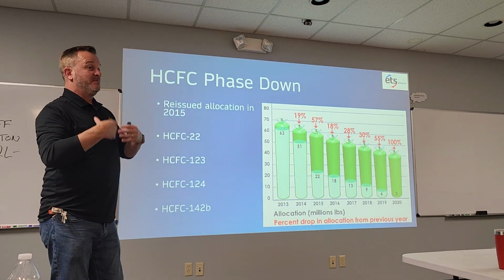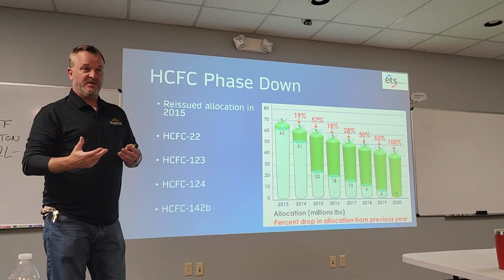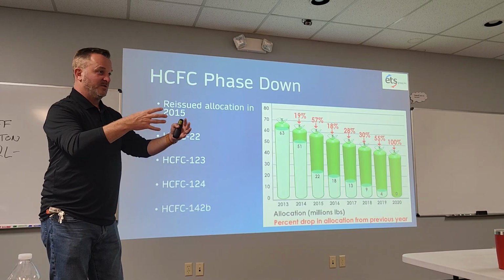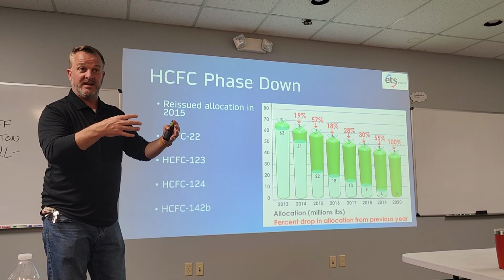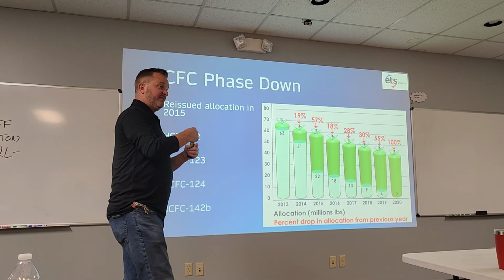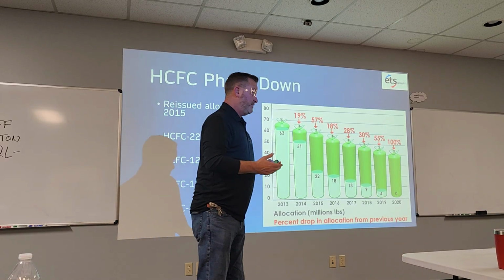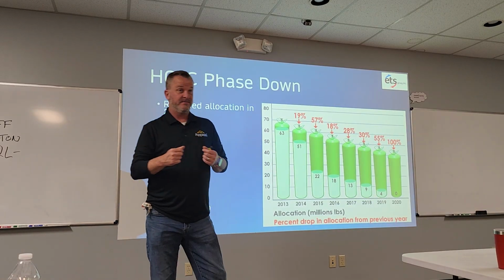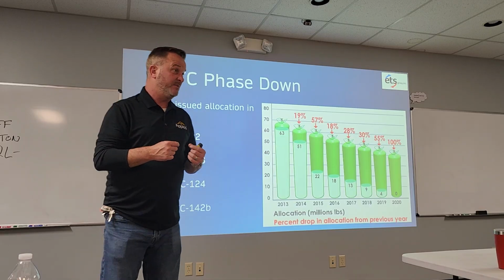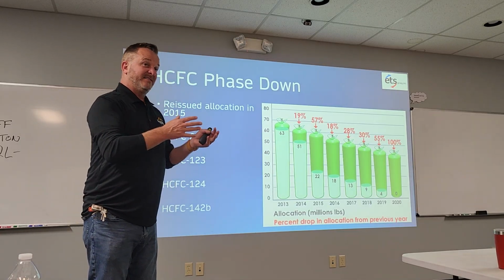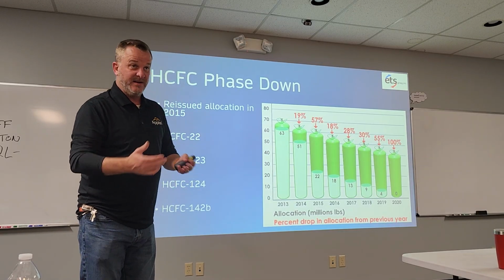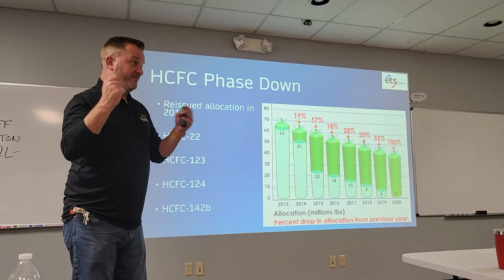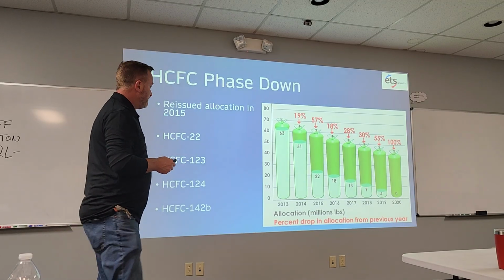So if there's one thing I can push, it's that when you're recovering refrigerant, try to keep it as close to one single refrigerant as you possibly can. Because if you want prices to stay low on these refrigerants that aren't manufactured anymore, that's a big factor - it costs a reclaimer a lot of money to separate these things out and clean them up. And the more gas they get that they can't reclaim, if it's too mixed, they've got to burn it off and let it go.